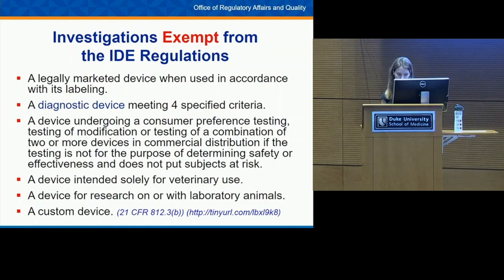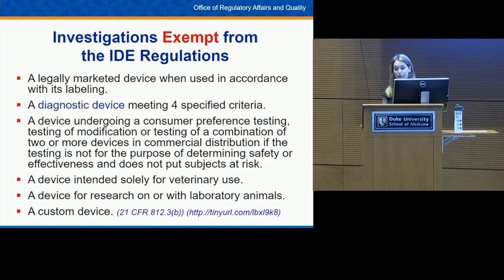Custom devices have very specific requirements: they must not be generally available, are usually made specifically for a particular physician or dentist, cannot be used in more than five patient cases per year, and have annual reporting requirements. It is generally rare for researchers at an institution like Duke to be developing a custom device. A guidance document with more details is available.